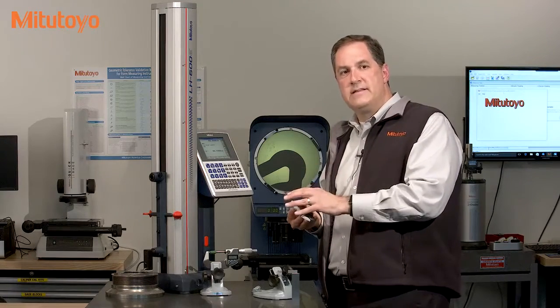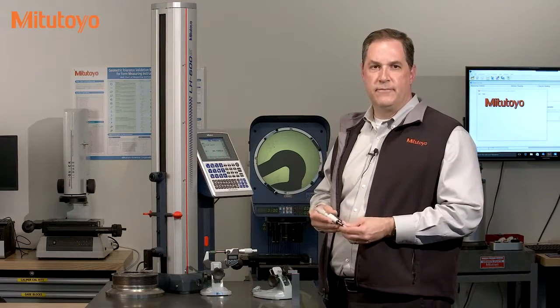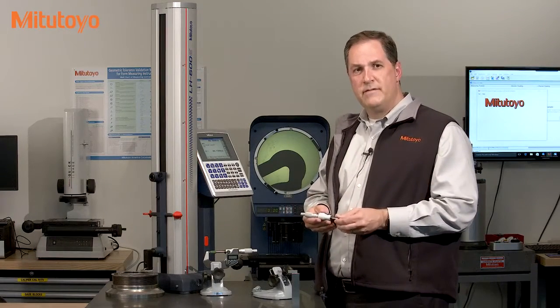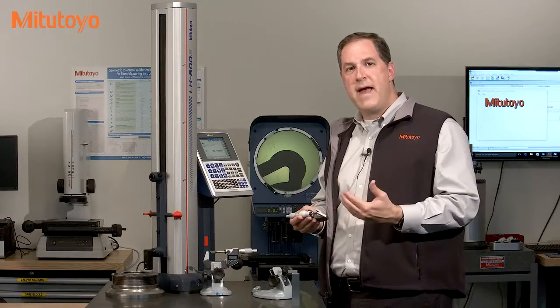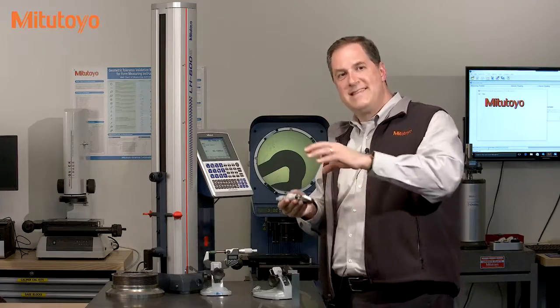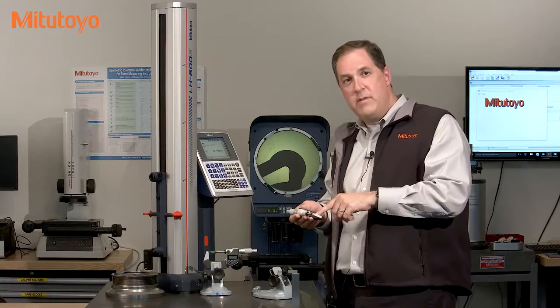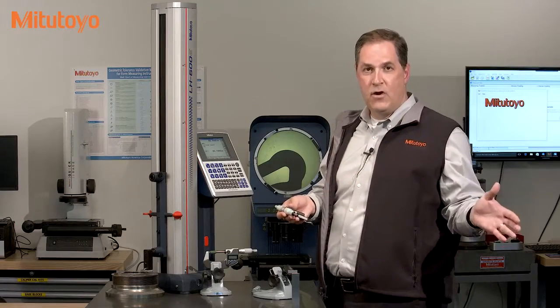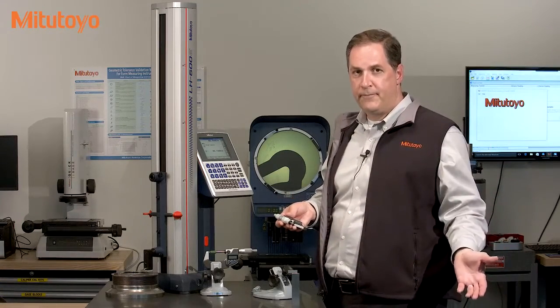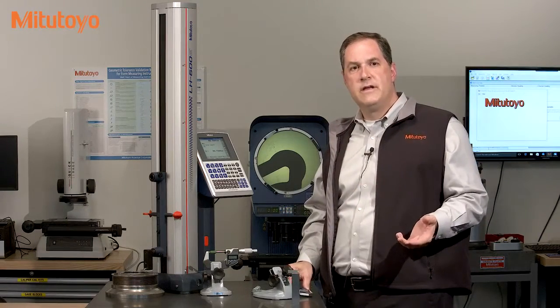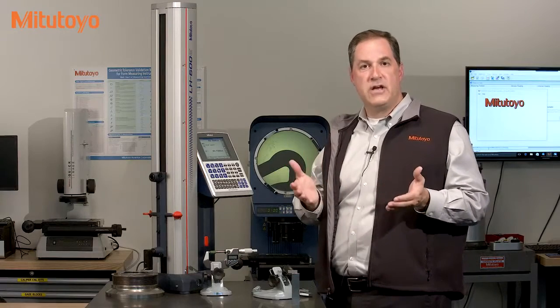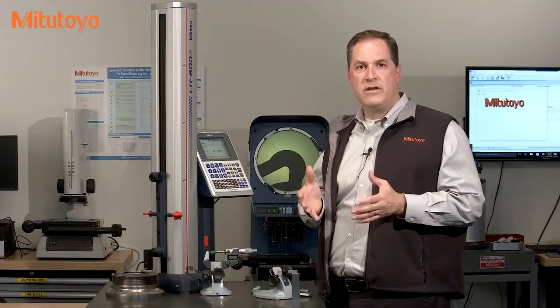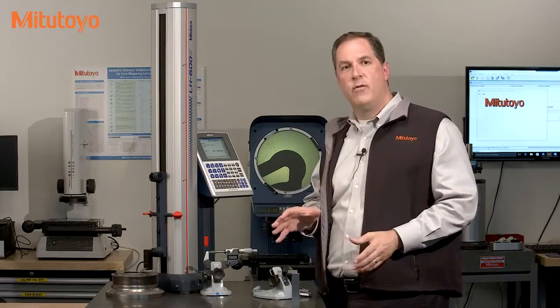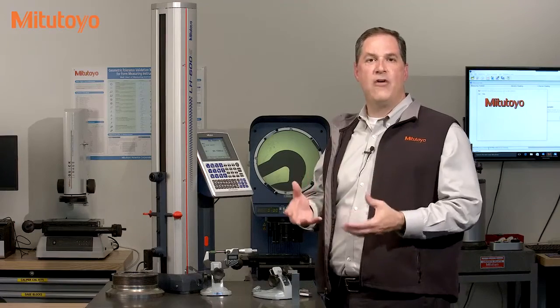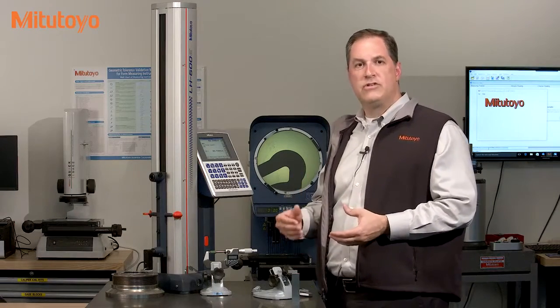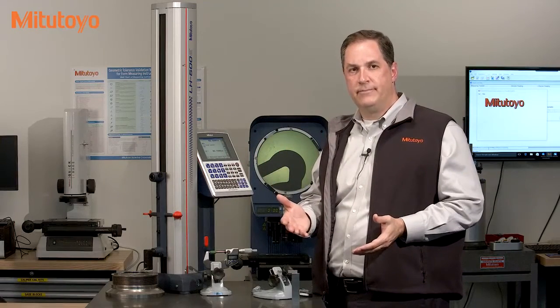If the as found data is out of tolerance, then you have three things you need to do. First, you need to determine if that out of tolerance condition has been impacting your product quality. What does this gauge being out of tolerance today mean for the measurements that you made just yesterday, or a week ago, or a month ago? Second, if the gauge is out of tolerance, maybe your calibration interval needs to be adjusted to prevent that from happening again. Calibration intervals should be based on the historical performance of the measuring instruments, and the as found calibration results are the key data used to lengthen or shorten calibration intervals.